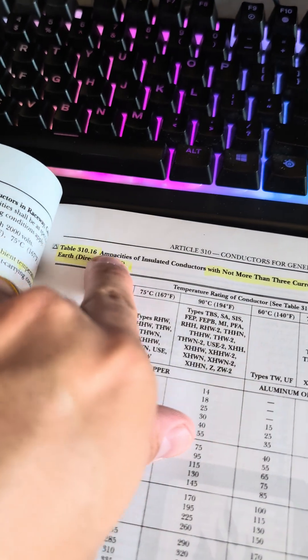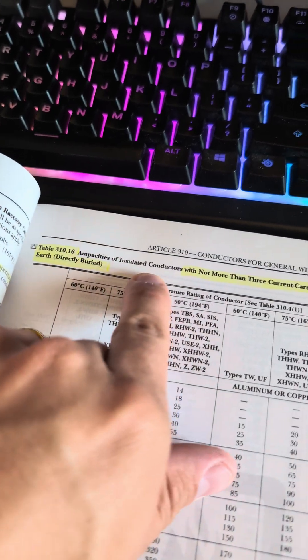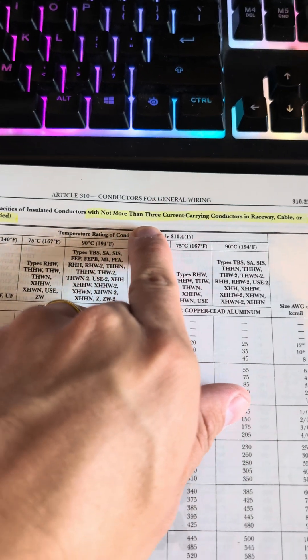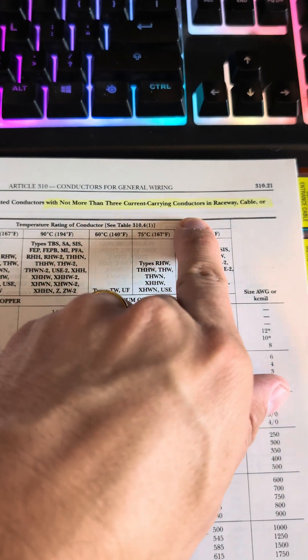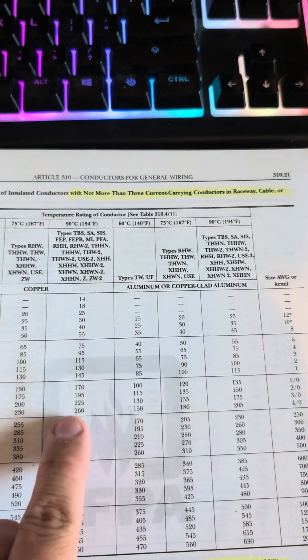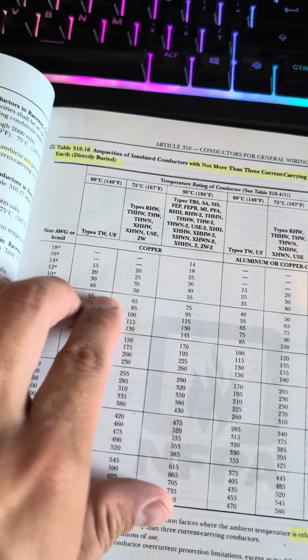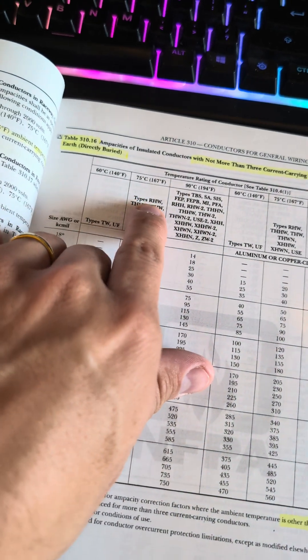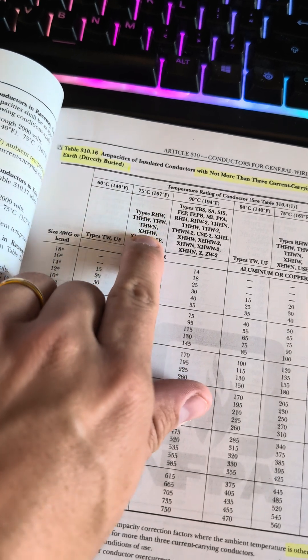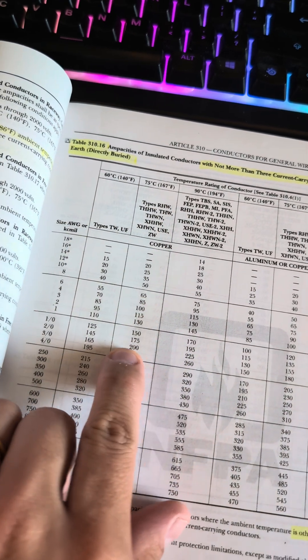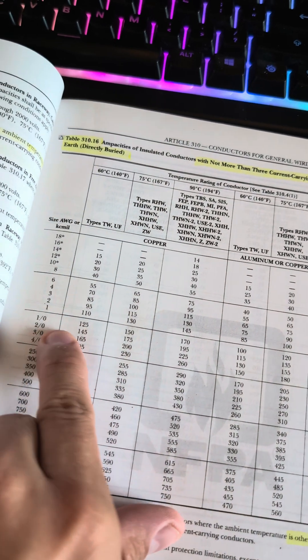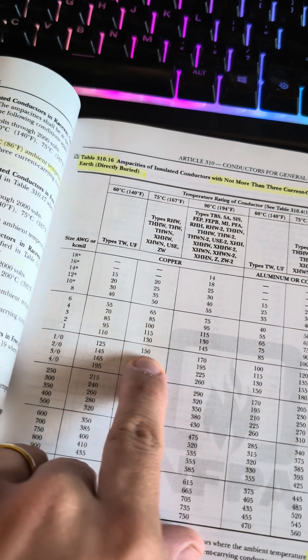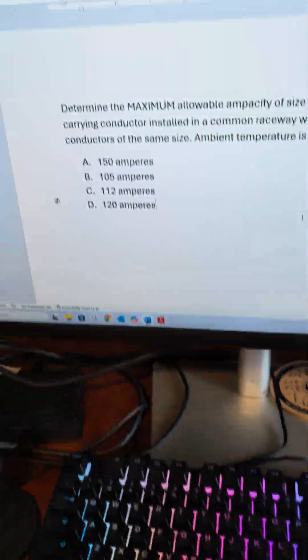This is the ampacity of insulated conductors with not more than three current carrying conductors in a raceway, cable, or earth. We're going to look for THW wire, which is 75 degrees C, and then we're going to look for 1/0. We find 150.